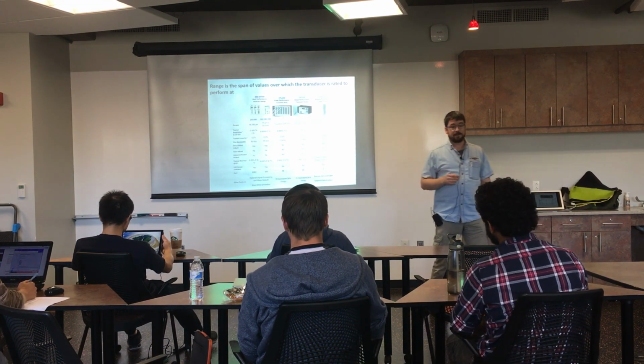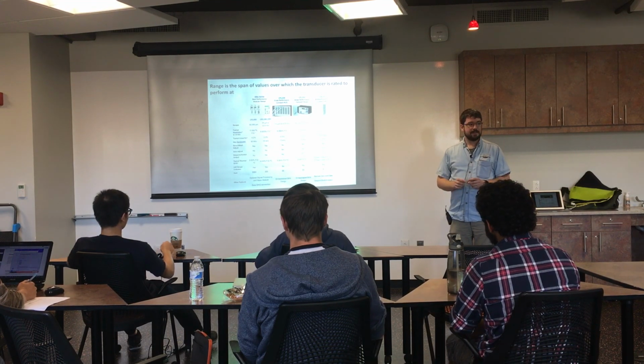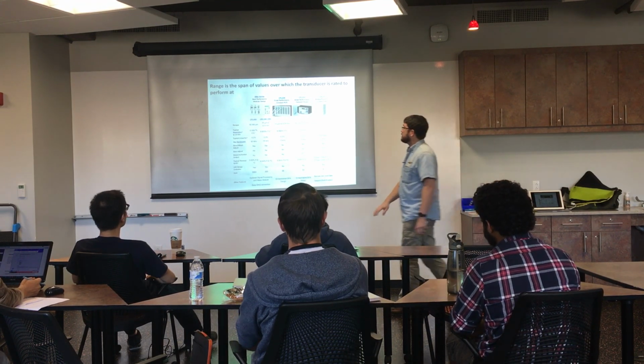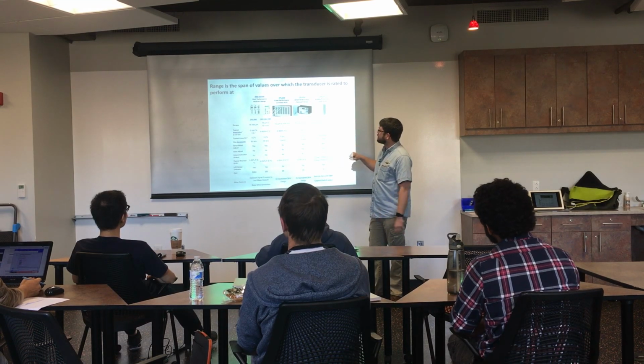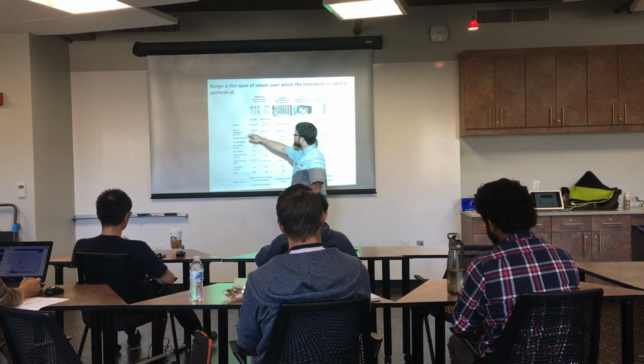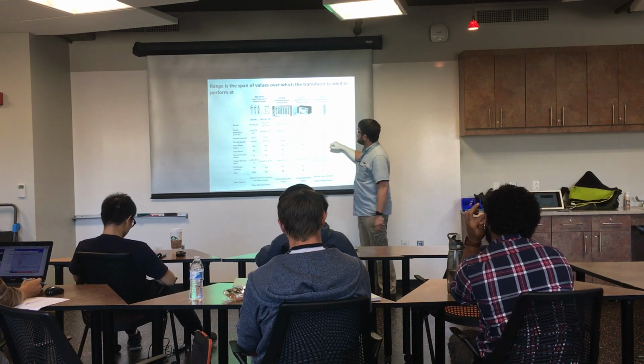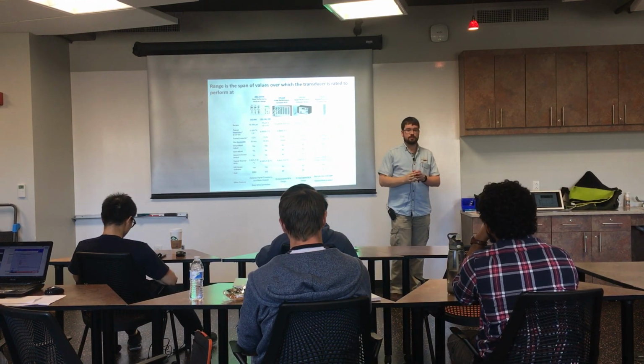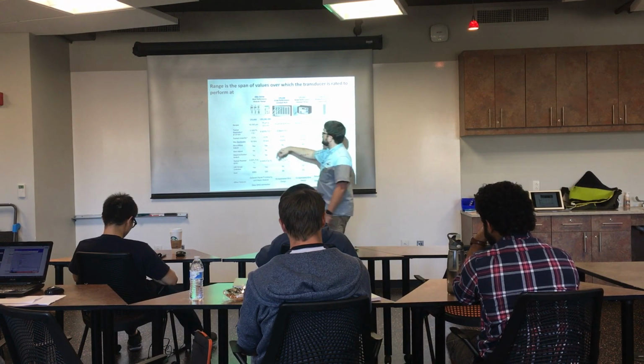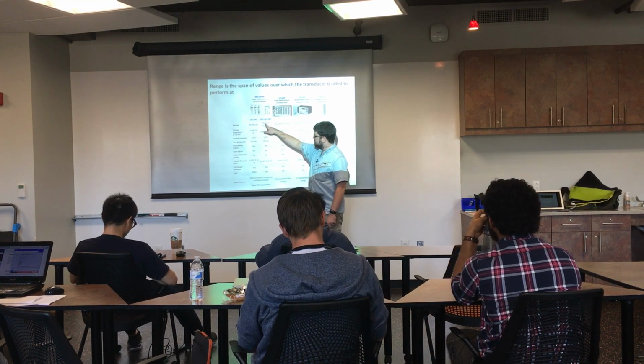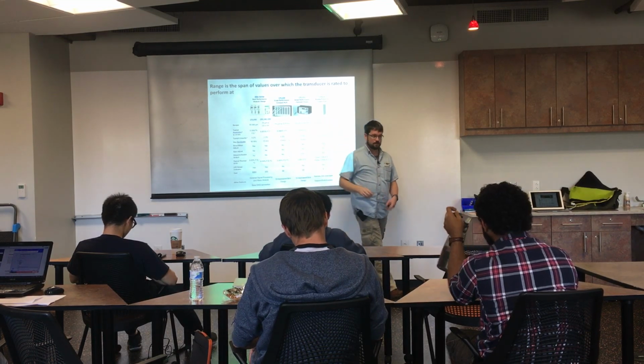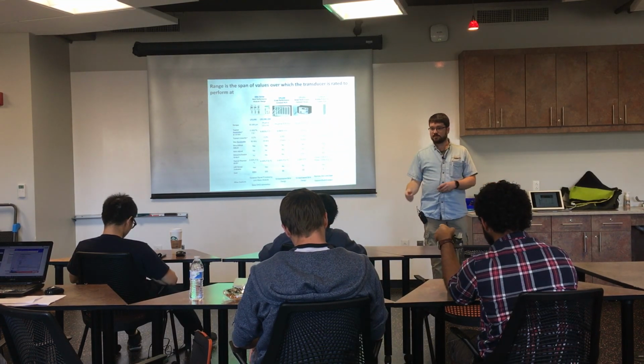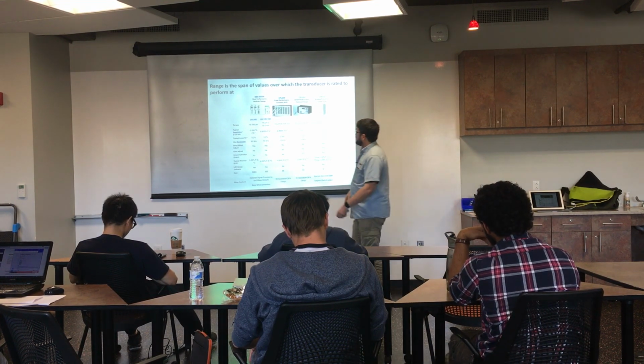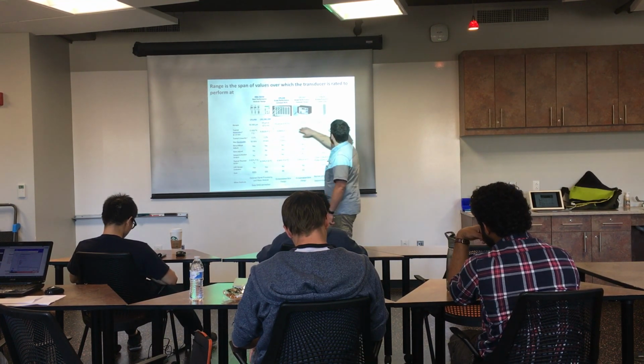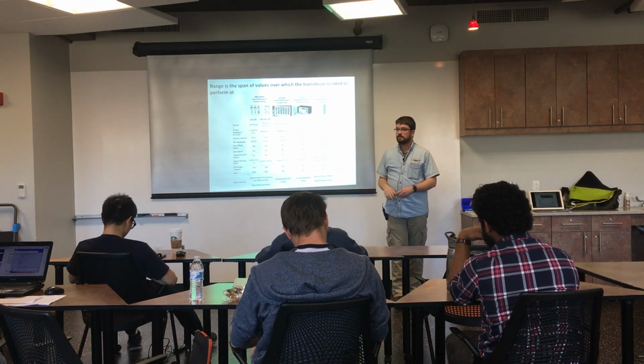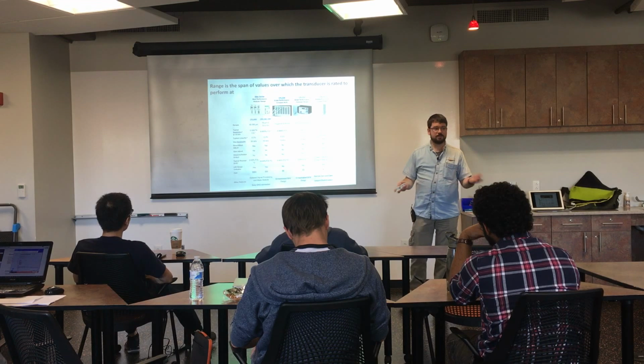The first one, and the thing that actually will cut most transducers out of the running, is what range you need. So this is from a manufacturer of proximity and distance sensors on their website. And here they have a range row that tells you over what range this transducer will work, what it can sense. So here, 100 to 200 microns displacement, or here 10 microns to 12.5 millimeters displacement. So if you need something that measures meters of displacement, maybe this isn't the one for you. If you need just a few hundred microns, you could go over here. Up here, 50 microns to 12.5 millimeters would be one of the larger ranges that they offer. So range is a pretty simple concept.